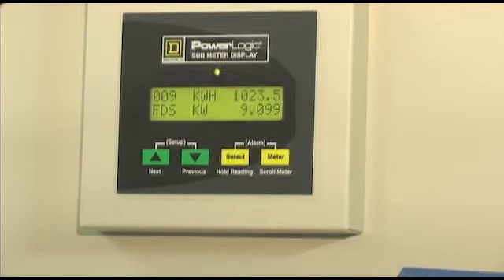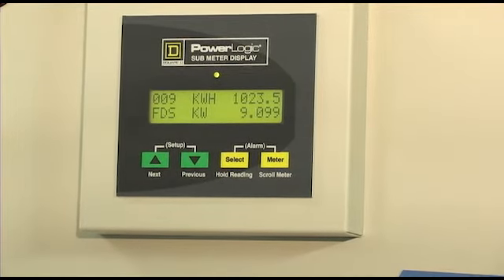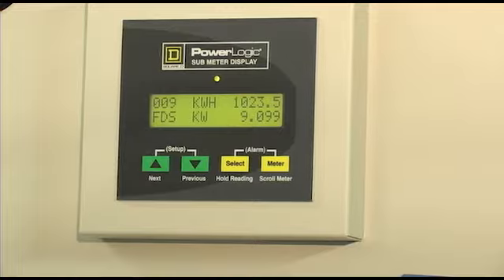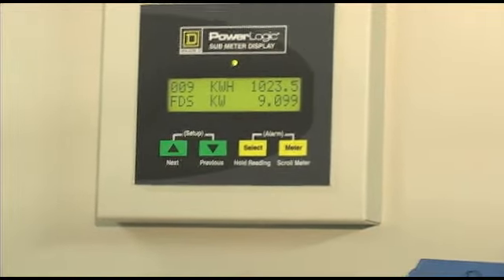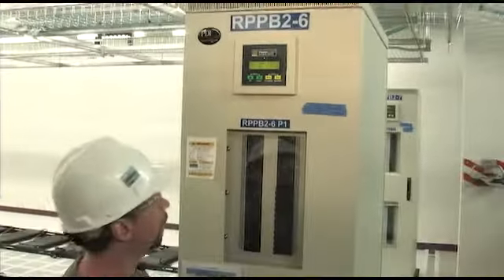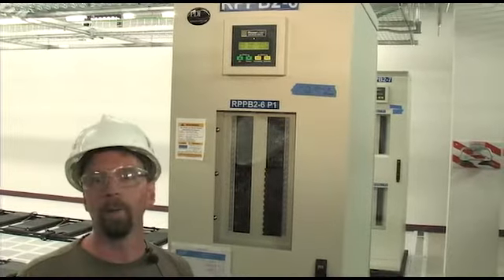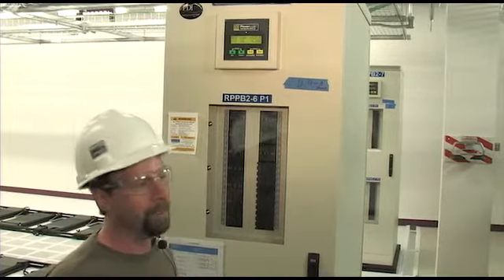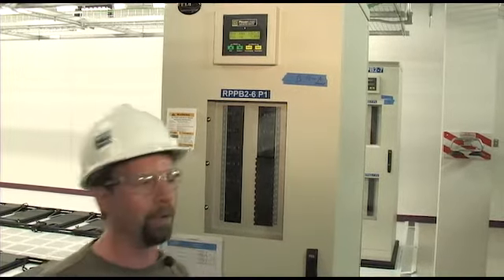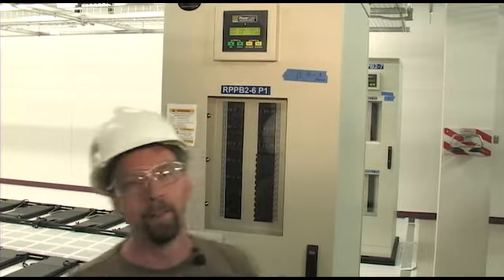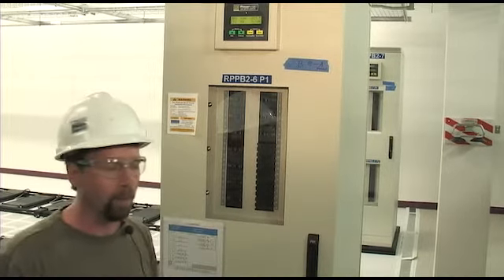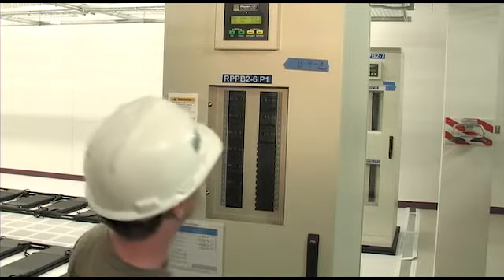On your remote communication, you'll have more information than this. You should have like peak current and all that, amongst other alarms, so you can see more information to find out if you get an alarm on high current, you can figure out what the problem is. And obviously, most of the time it's not really a high current, or somebody plugged something in. Sometimes that does happen where you did have an overcurrent. And I think that's basically it.